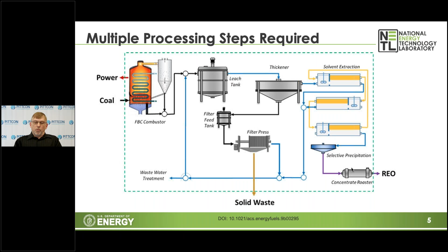So there are methods for measuring REE concentrations. The go-to technique is inductively coupled plasma mass spectrometry, ICP-MS. That's the go-to technique. Great detection limits, parts per trillion. The issue for a process situation, though, is that the instrument costs a lot and it's not portable. You have to take a sample from the process, bring it to a lab, treat it in some way, put it in an instrument. This involves time and there's no immediate feedback.